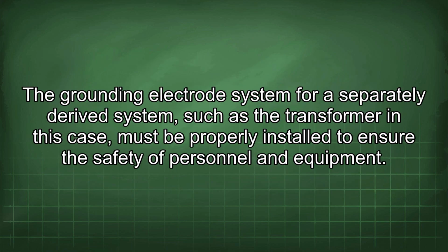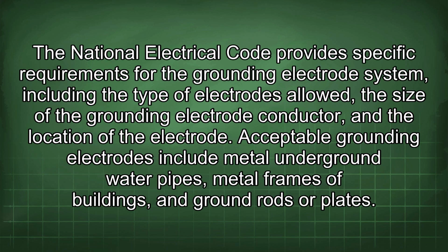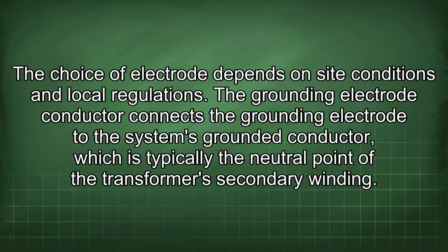The grounding electrode system for a separately derived system, such as the transformer in this case, must be properly installed to ensure the safety of personnel and equipment. The National Electrical Code provides specific requirements for the grounding electrode system, including the type of electrodes allowed, the size of the grounding electrode conductor, and the location of the electrode. Acceptable grounding electrodes include metal underground water pipes, metal frames of buildings, and ground rods or plates. The choice of electrode depends on site conditions and local regulations.